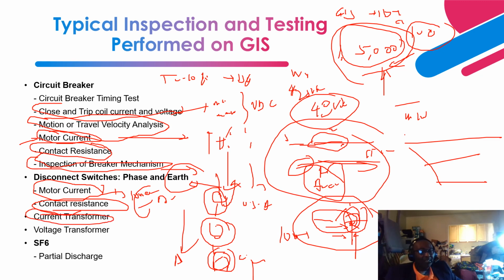Next is inspection and testing of the current transformer. For the current transformer, what testing is done? Insulation resistance testing, to test the insulation medium of the CT. Then turns ratio testing is done. Then magnetization testing to test for the saturation of the CT. Then also polarity testing is done to test the CT polarity. Next is the voltage transformer. For the voltage transformer, turns ratio testing is done, insulation resistance testing is done, then winding resistance testing is done. Same applies to the current transformer. Winding resistance testing is done. Then polarity, then phase shift testing is done.